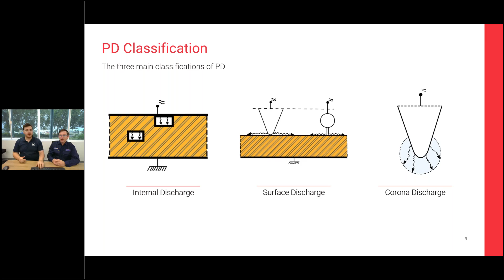That's why, when we talk about the hardware itself, you will see that we primarily focused on the TEV method. It's important to note that when we were discussing what technology we would use, we trialed several different methods: the PD Hawk, which is predominantly UHF, the transient earth method, as well as the acoustic. So it's important to use all those different methods to narrow down the best solution for your asset. One thing where it did come from is that Powerlink has been a very big adopter of UHF testing. It's what they use quite predominantly in their field testing and day-to-day hand testing. But for monitoring, it wasn't as viable, so we chose to go with another method. I'll talk about why we did that in a second.